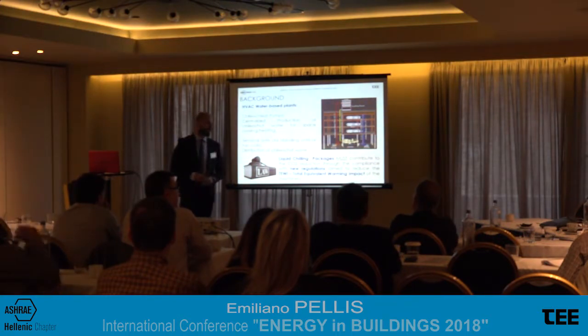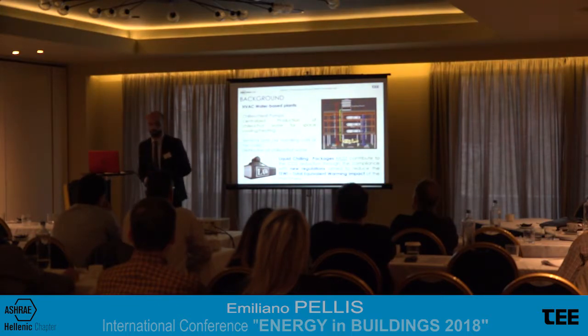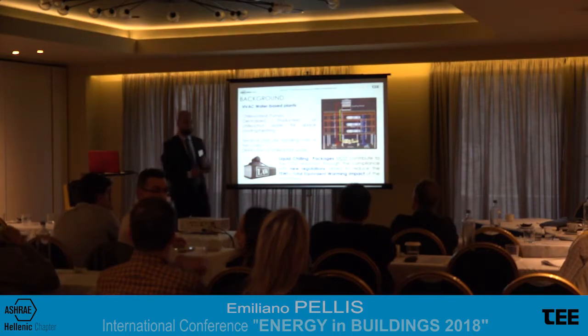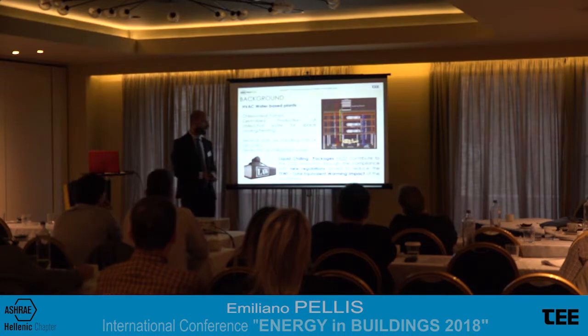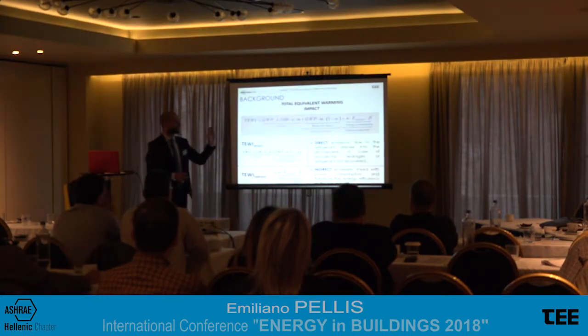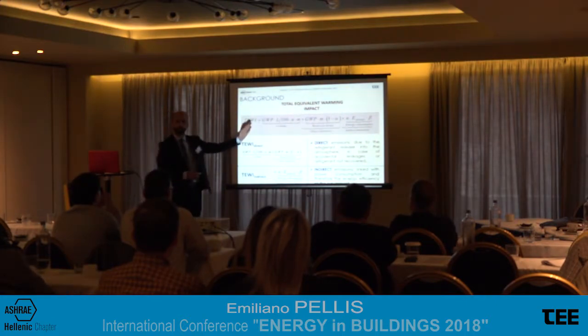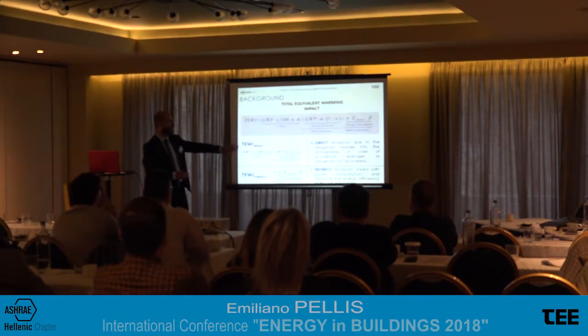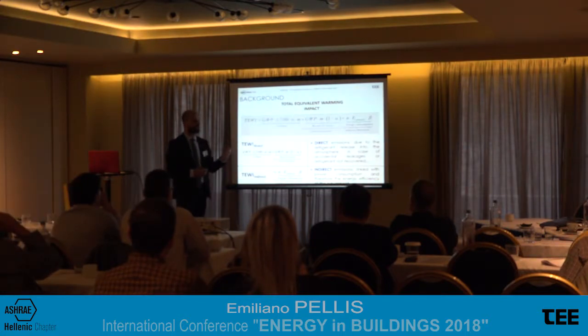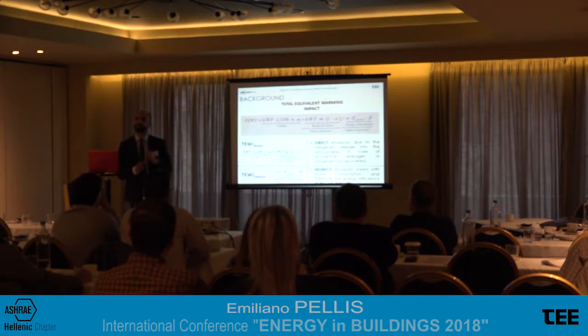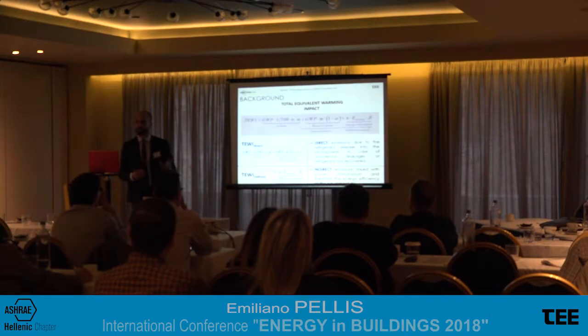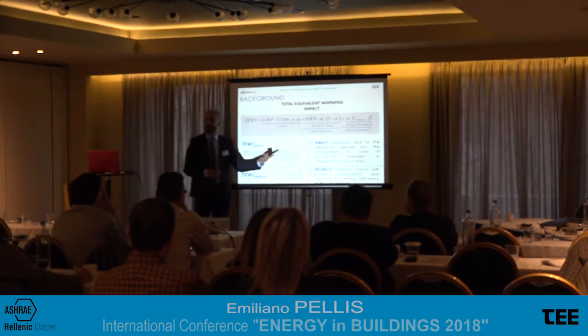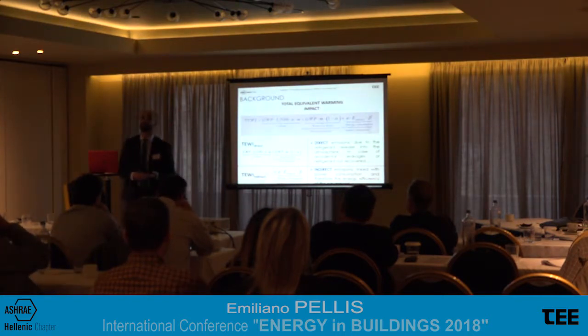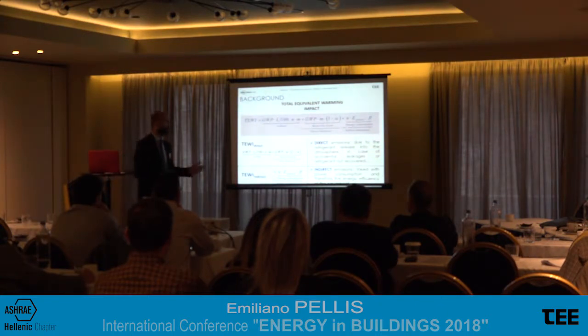So in particular, the chillers must contribute to the CO2 phase-down schedule through compliance with some new requirements coming from the new legislation. The new requirements are basically imposing the reduction of the TEWI for the chillers. TEWI is the total equivalent warming impact. You see in gray the complete formula for the TEWI, and we can separate two contributions, what we call the TEWI direct and the TEWI indirect. The TEWI direct is related to the direct emissions of CO2, basically the direct release of refrigerant into the atmosphere, for example in case of an accidental leakage or refrigerant not recovered at the end of the life cycle of the machine. The TEWI indirect is related to the indirect emission of CO2, linked basically with the energy consumption of the unit and therefore with the energy efficiency of the unit.